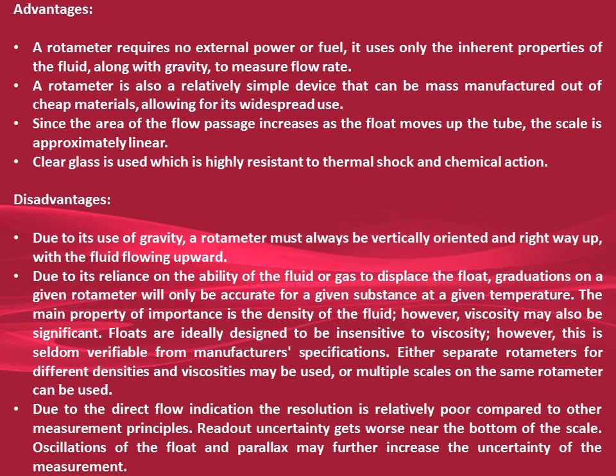Either separate rotameters for different densities and viscosities may be used, or multiple scales on the same rotameter can be used. Due to the direct flow indication, the resolution is relatively poor compared to other measurement principles. Readout uncertainty gets worse near the bottom of the scale; oscillations of the float and parallax may further increase the uncertainty of the measurement.